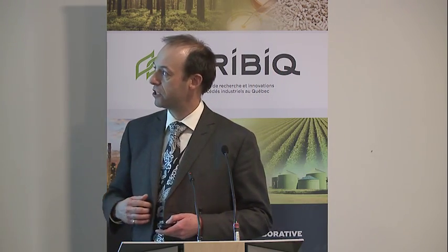Next step. We are now at the equipment design and the specification of those. So the process and the mechanical engineer. It's the first time you see the mechanical engineer here. They have to calculate the size of the equipment, so they will use the dimensionless variables we talked about a few minutes ago. They will size the piping, size the pump, and determine the specification for the material. Will it be steel, stainless steel, HDPE, all of those. Material finish: what is the roughness of the material you want to work with? Is it crucial? Is it critical?